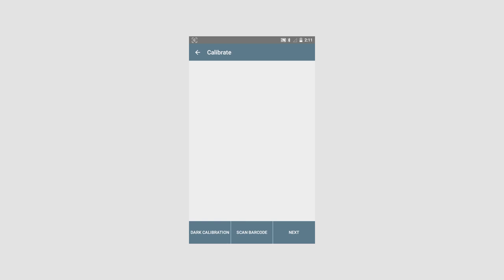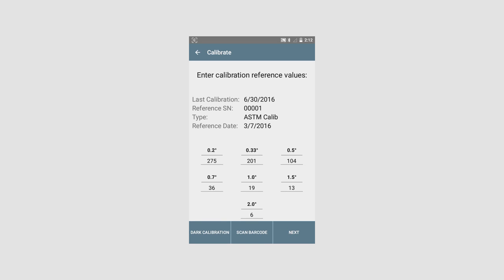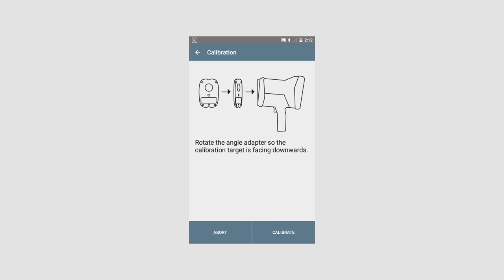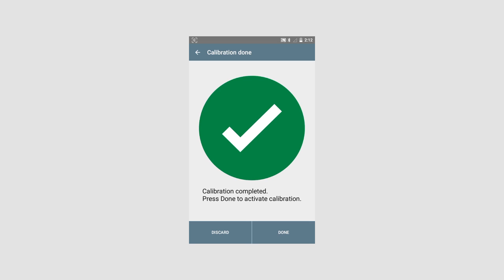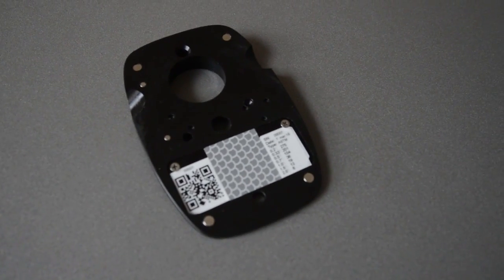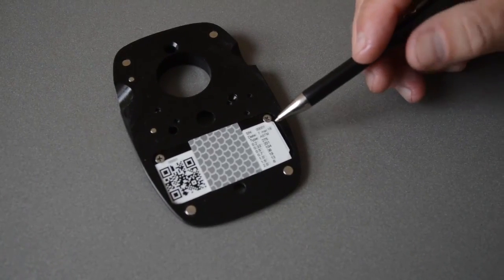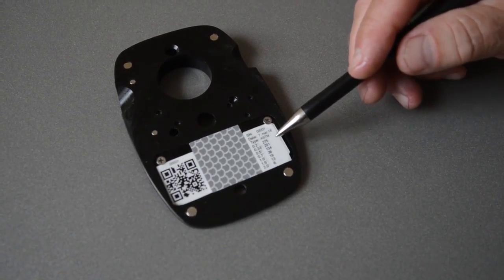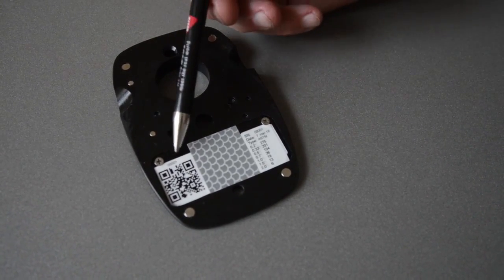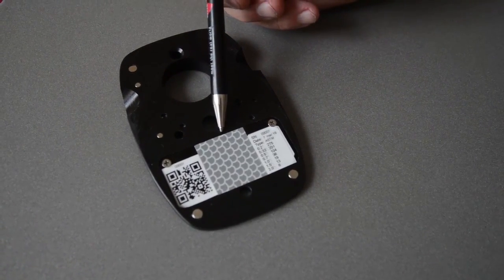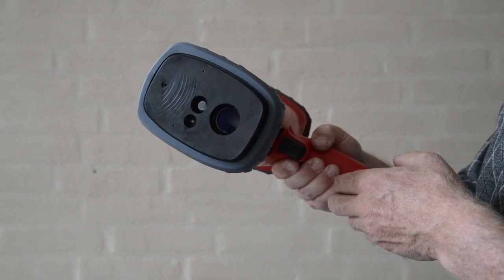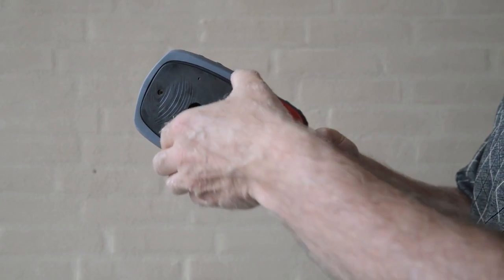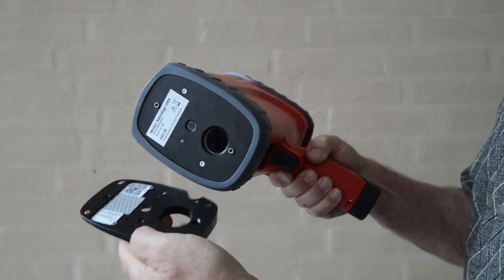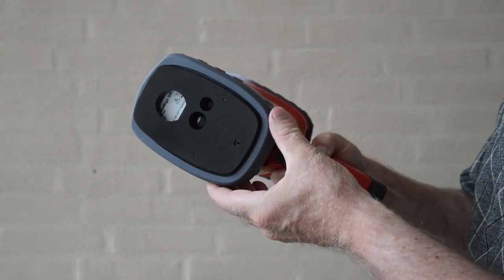The instrument will automatically focus and capture the different values. Next step is to mount the calibration reference on the front of the instrument, do the calibration, and within 1 or 2 seconds, calibration is done. The relevant tools for doing a calibration are located on the back side of the angle adapter. Here you can locate the values to calibrate up against for the different observation angle, the barcode for the scanning, and the calibration target where the actual calibration is done. When the calibration figures have been entered into the instrument, the angle adapter with the calibration target on the back has to be turned around to be able to make the calibration.